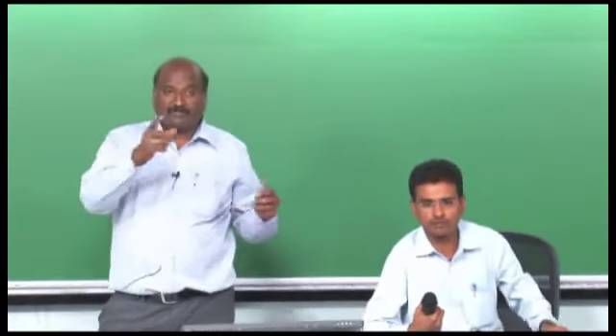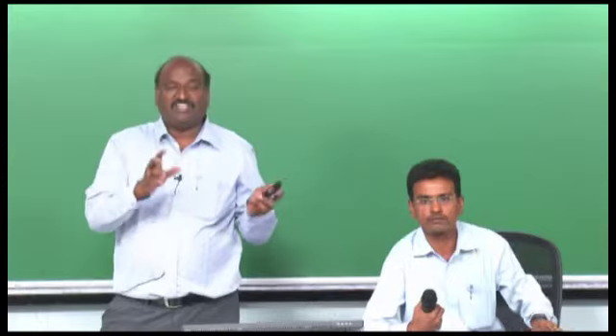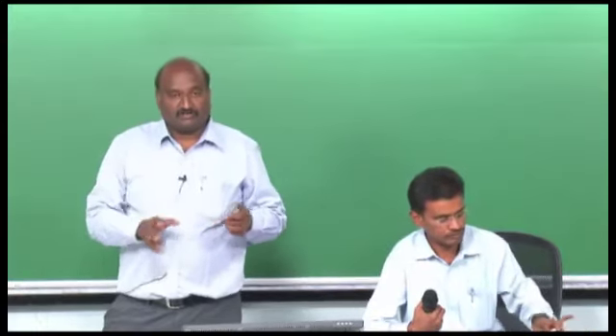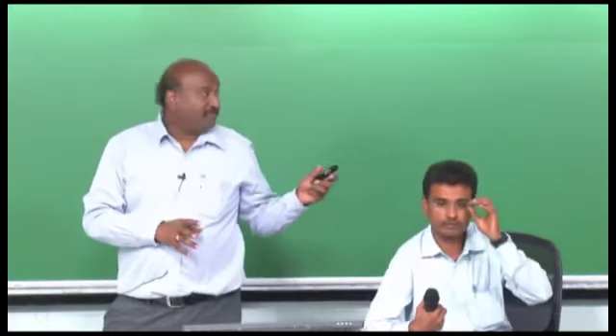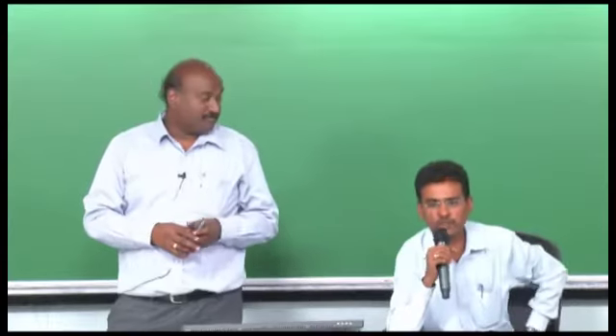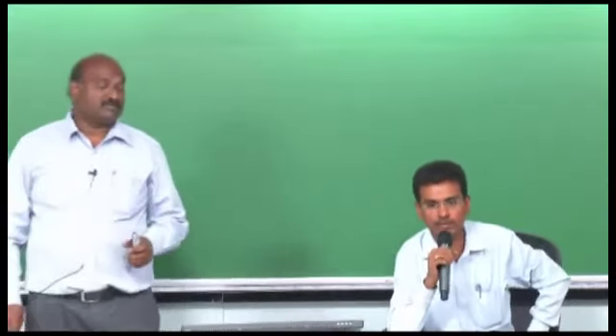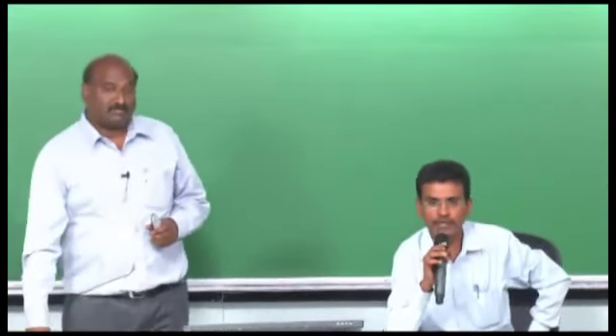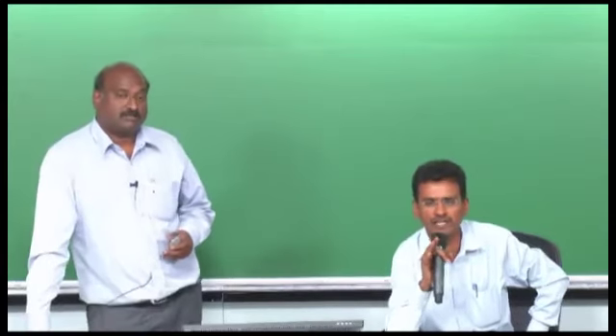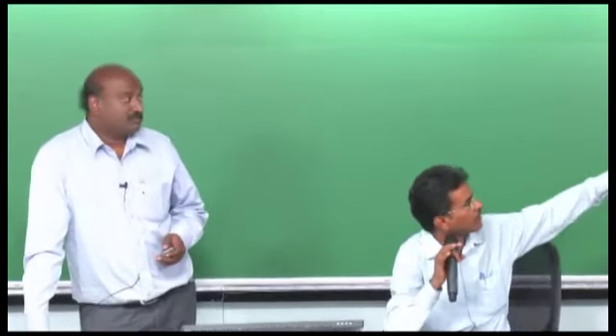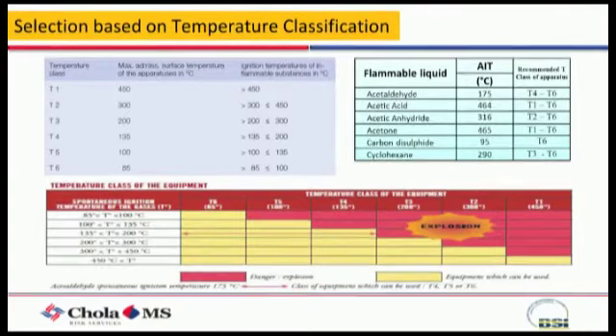That's all. Depending upon their AIT, you have an EXD temperature rating. T4 or T5 can be the product. For petrol or diesel also AIT is available. If I remember correctly, that's coming around 200. So normally what they will do is select equipments of T4 or T5 or T6. Mostly it will be in the range of T4.